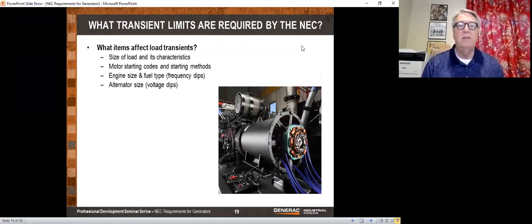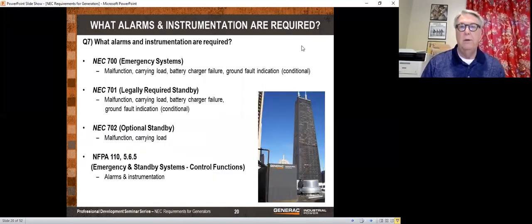What items affect the load transients? The size of the load and its characteristic, motor starting codes and starting methods, engine size and fuel type, and the alternator size. So if you're starting a big motor, you could reduce the voltage drop by going with a bigger alternator. Doesn't need to be a bigger engine, just a bigger alternator. Or you could go with a different type of starter on the motor. And we do both, depends on the situation.